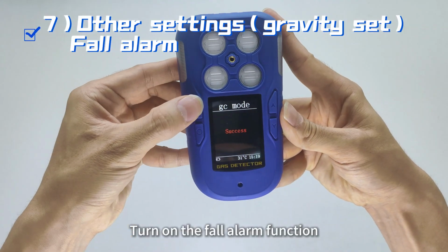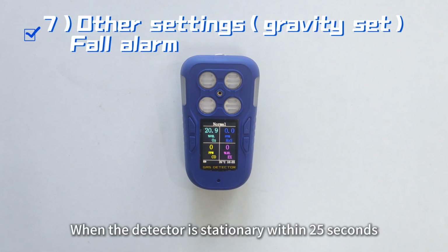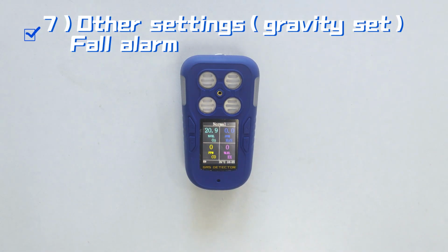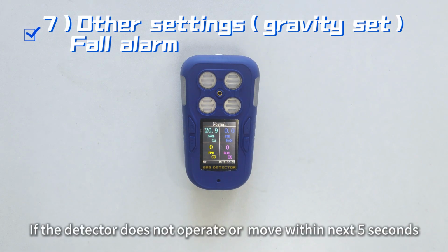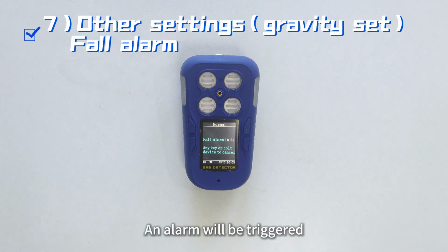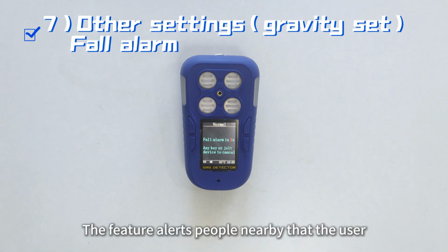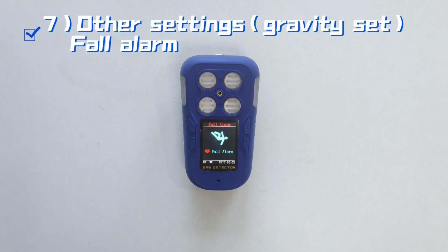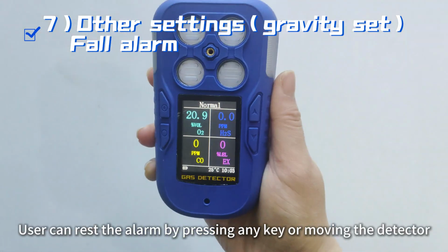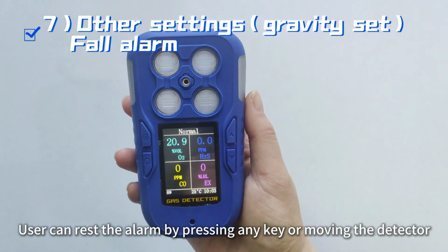Turn on the fall alarm function. When the detector is stationary within 25 seconds, the warning as shown will appear. If the detector does not move within the next 5 seconds, an alarm will be triggered. The feature alerts people nearby that the user may have fallen and be in danger. At this point, the user can reset the alarm by pressing any key or moving the detector.